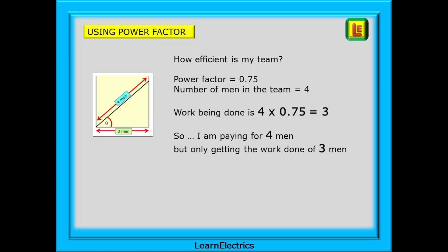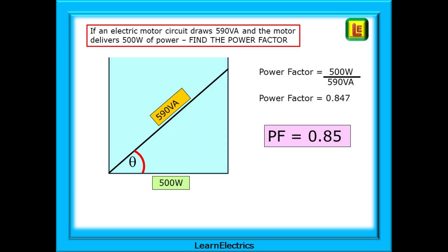The apparent power is four workers, but the actual power is only three workers, and cos theta tells us the power factor — 75% efficient. Back at the office, the boss knows the power factor is 0.75 and there are four men, so actual work done equals four multiplied by 0.75, which is three. For an electrical example: if an electric motor circuit draws 590 VA from the source and the motor delivers 500 watts, find the power factor. Adjacent over hypotenuse: 500 watts divided by 590 VA gives 0.847, which rounds to 0.85 or 85% efficiency.